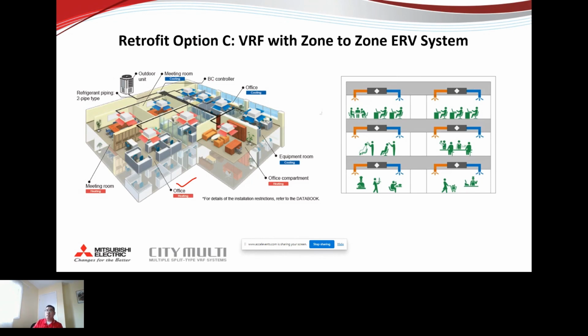Therefore, it is comfortable and efficient, and refrigerant piping is significantly smaller than air duct. Therefore, we are also able to run the piping with minimum interference to the existing equipment on site. And on top of that, we're using the zone-to-zone ERV that you can see over here. We are dividing the office into different zones, so let's say the technical service area, the accounting area, the general office area. Then, depending on your occupancy, depending on the day, depending on the time, we can increase the fresh air for that specific zone or decrease it.